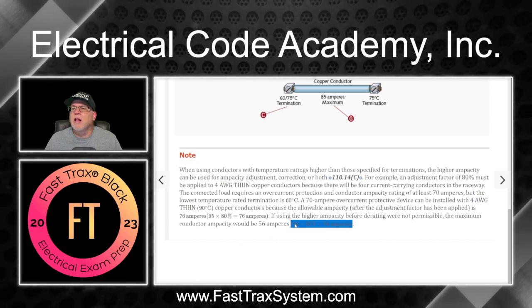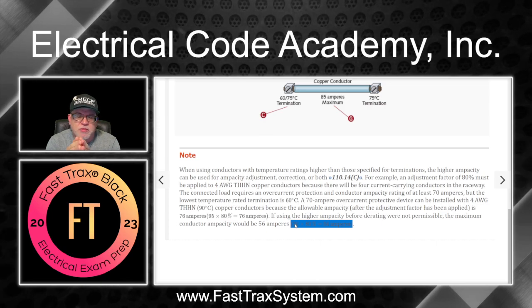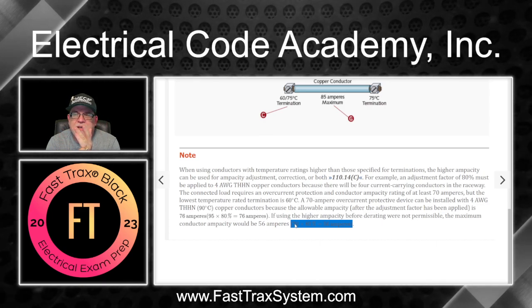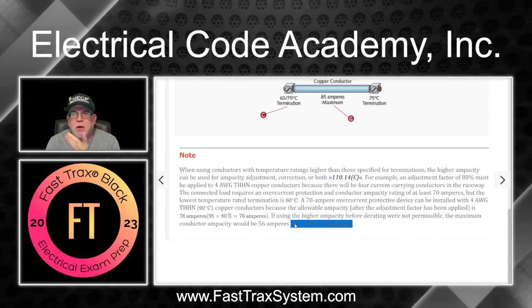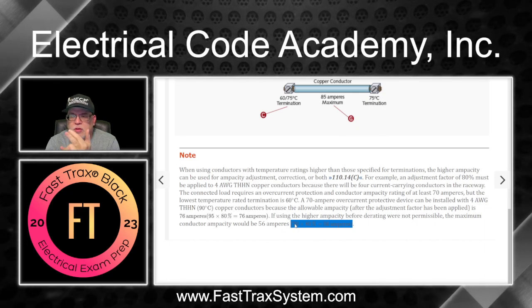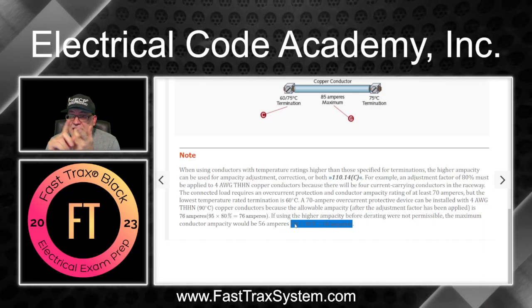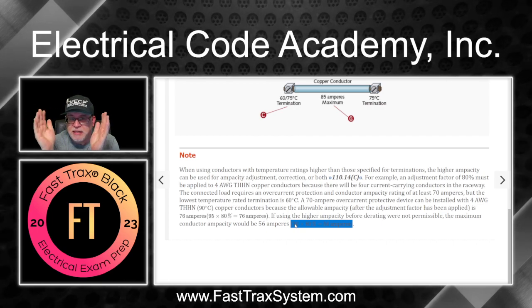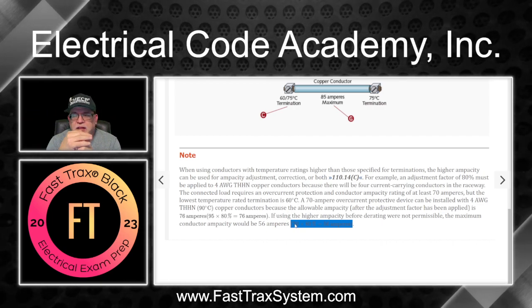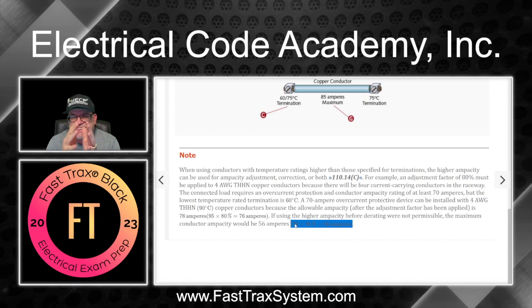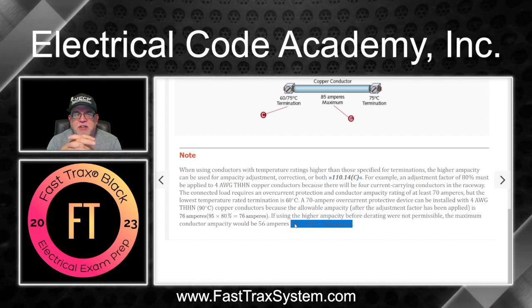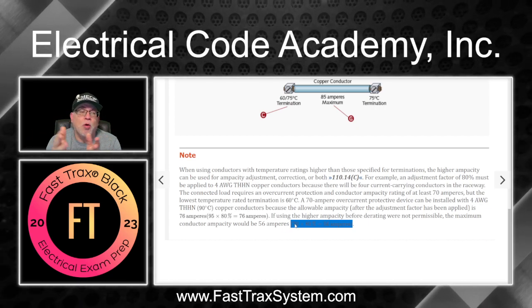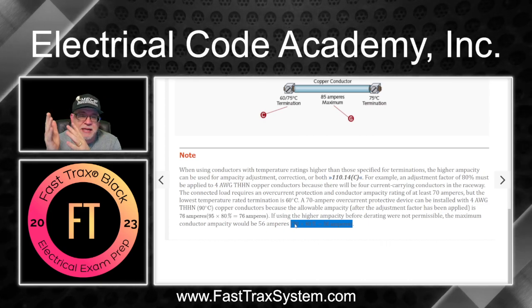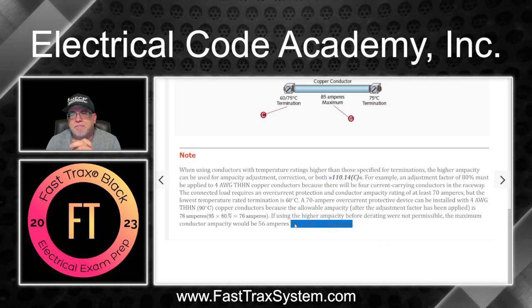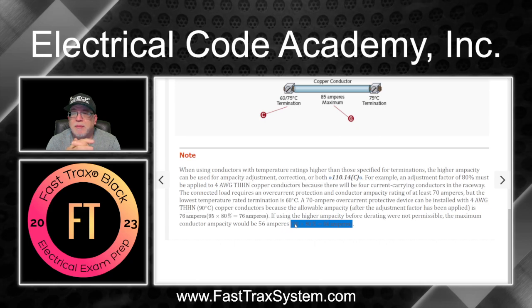So this is why it's so important, folks, to keep in mind when you're dealing with the terminals, the conductor's insulation, and the end terminals. Think of it as 3 separate pieces in this kind of weakest link theory. Hopefully that makes sense to you. Now, if you're dealing with over 100 amps, then you're just automatically going to go to the 75-degree column, right?